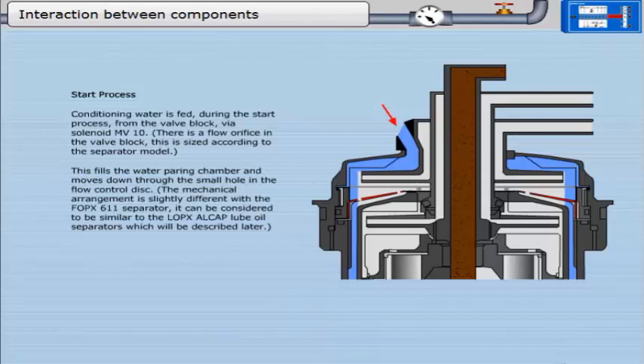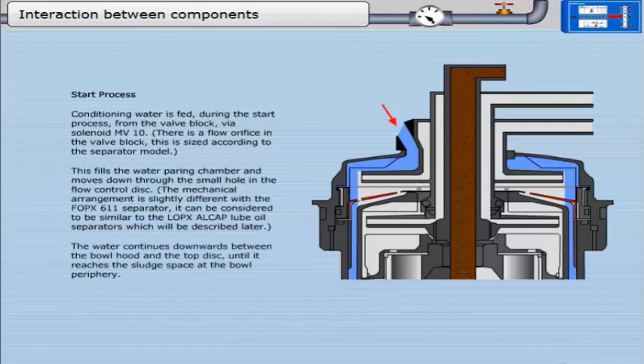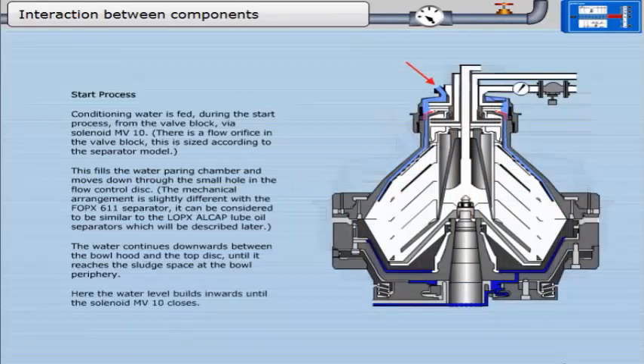The mechanical arrangement is slightly different with the FOPX611 separator; it can be considered to be similar to the LOPX Alcap lube oil separators, which will be described later. The water continues downwards between the bowl hood and the top disc, until it reaches the sludge space at the bowl periphery, where the water level builds inwards until solenoid MV10 closes.